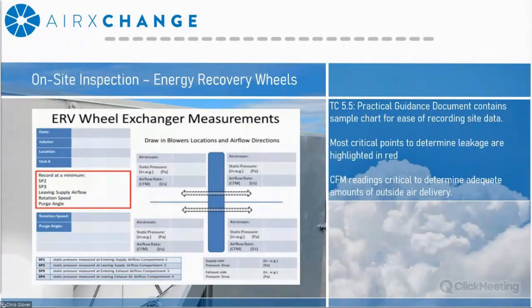And also, equally important, you're going to want to take down the outside airflows, because that's going to determine if you're receiving adequate amounts of outside air delivery. You want to make sure that you're maintaining those minimum ventilation rates.